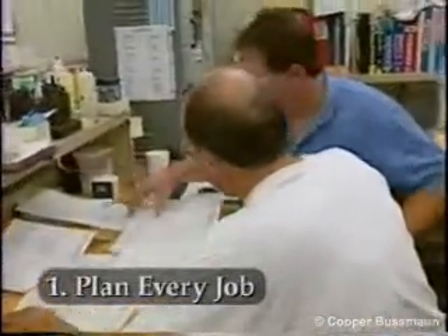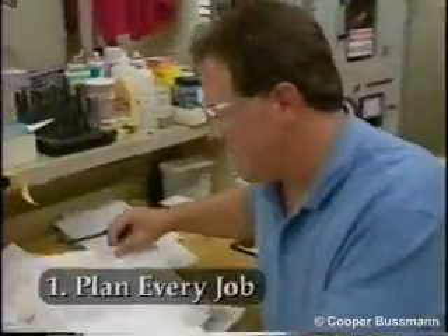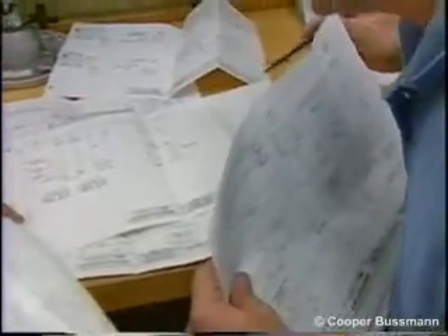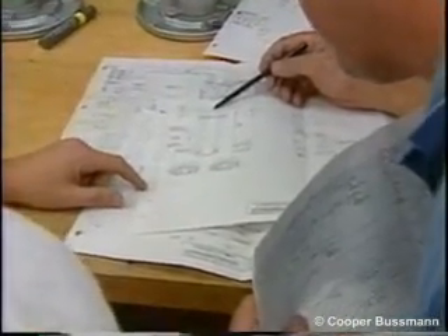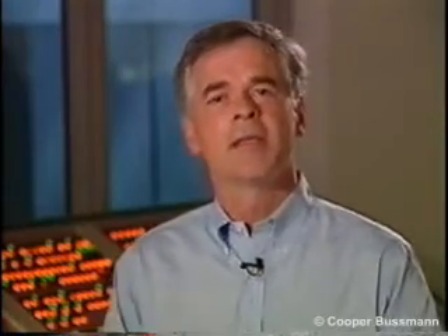Electrical safety starts with education and training, planning for each job, and preparing written procedures. To reduce electrical hazards, we need to address each hazard as the work is being assigned and planned. Here are some principles that will help ensure a safe workplace. Plan every job. Most accidents occur when something unexpected happens. Take the time to prepare a plan that considers all possible eventualities. Before you start the job, think about each step and try to visualize the potential for a hazard. Conduct a flash protection boundary analysis. The NFPA 70E Section 2-3.3.3 has adopted a new requirement to define the safe work distance from potential arc hazards.